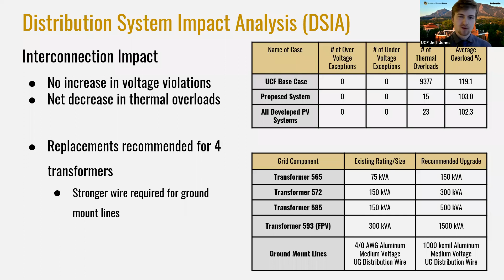But in the process of analyzing the thermal overloads, we also identified 3 different transformers on the UCF grid, as well as one existing transformer that was previously dedicated to the photovoltaic system. All 4 of these transformers were routinely experiencing thermal overloads well above their emergency limits. The second table here shows these 4 transformers' existing ratings and the ratings of our recommended replacements.